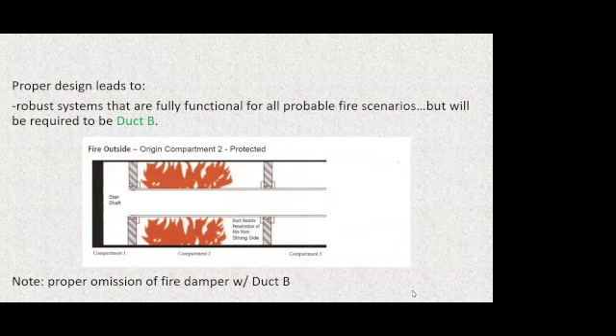We're going to need to understand some jargon. In the fire-rated duct industry, there are two different test standards, and they use different jargon to describe their test specimens. And those are things we need to look for in the product data, because if we don't understand that jargon and we aren't looking for the right jargon, we can't possibly be getting it right. So if you're not familiar with the terms duct A and duct B, when we're talking about the ISO 6944 test standard, if you're not familiar with condition A, B, C, and D, when we're talking about the ASTM E2816 test standard, then you can't possibly be getting this right, because they describe how the test specimen was tested. Was it tested on just one side, or was it tested on both sides? Because the code tells us very specifically which of those things we're supposed to be doing.